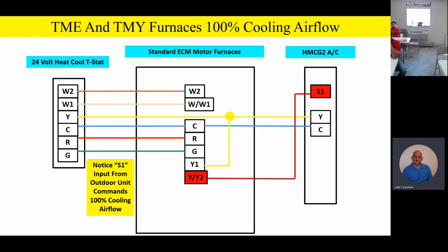But if it's below 60% capacity, let's say it's at 42% capacity, I'm just making that up, because it's a real mild day, then it'll kill that S1 signal, and the airflow drops back to 60% airflow on the indoor unit.